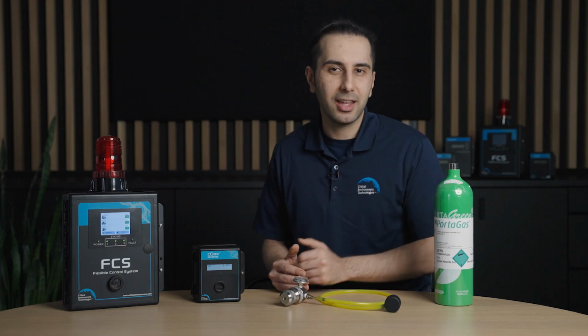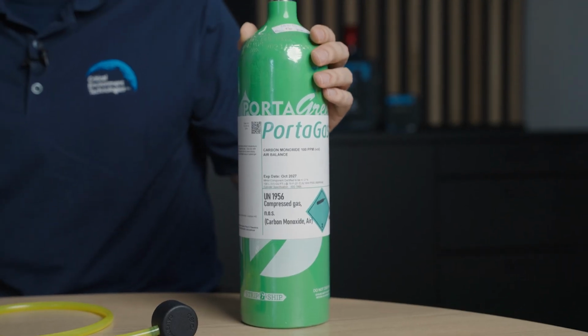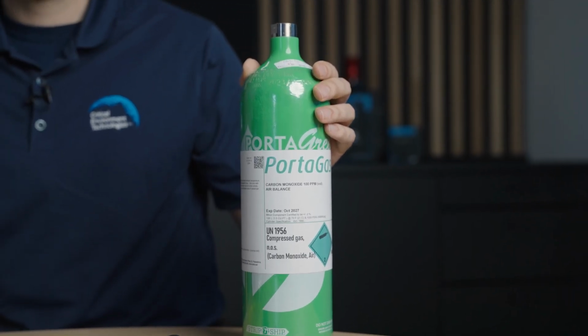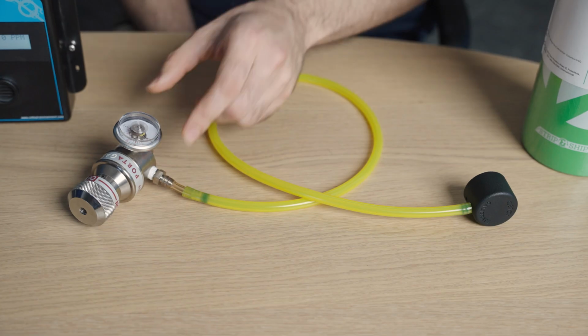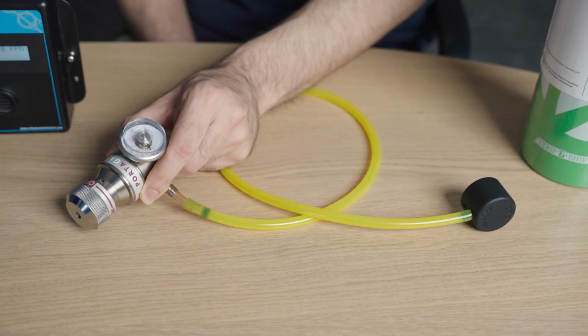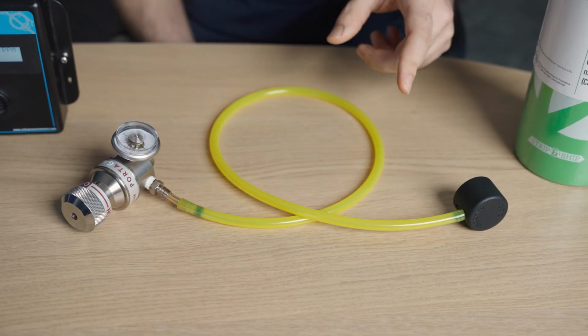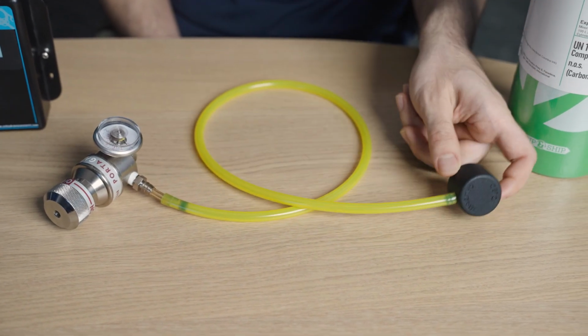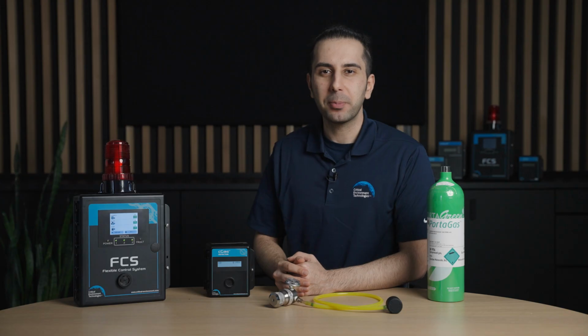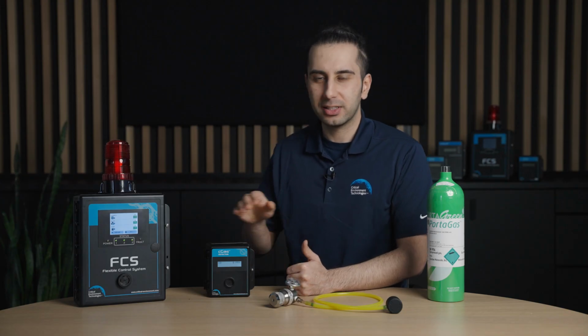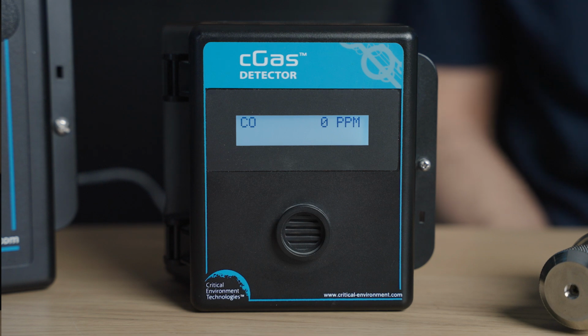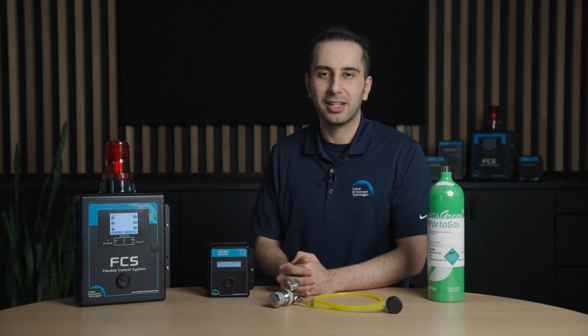Here we have a calibration gas cylinder, which should be a span gas that matches the target gas, a regulator, tubing, and a calibration clip. I will demonstrate the bump test on a C-gas analog detector with a carbon monoxide sensor. The procedure is the same on the digital C-gas detector.